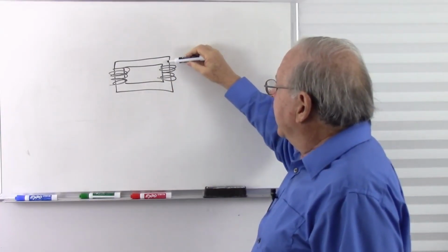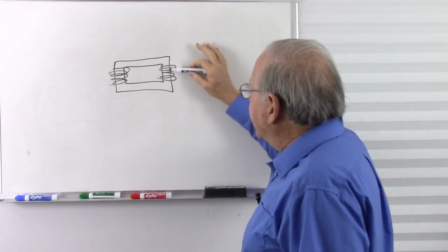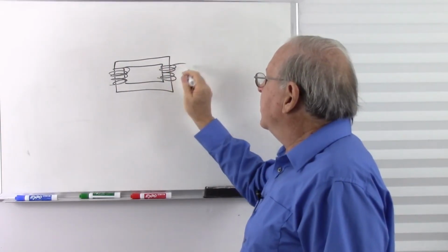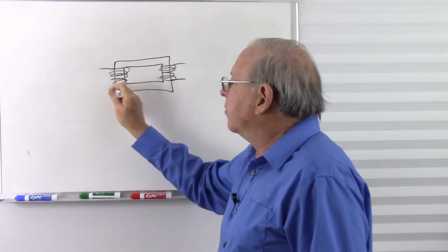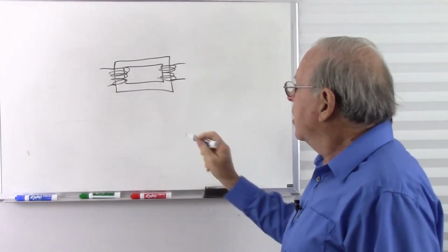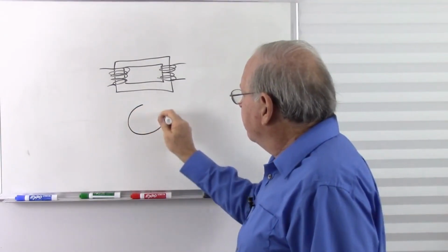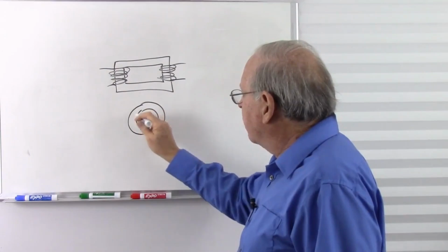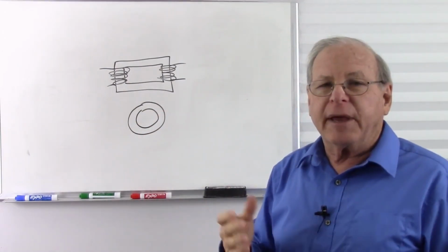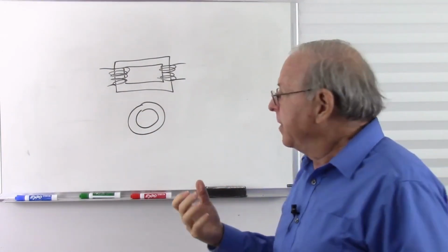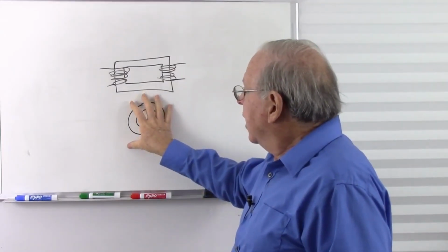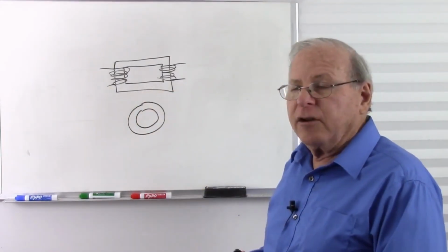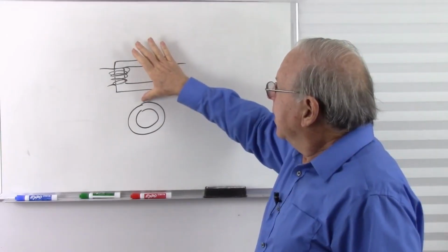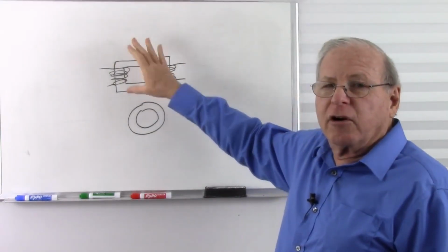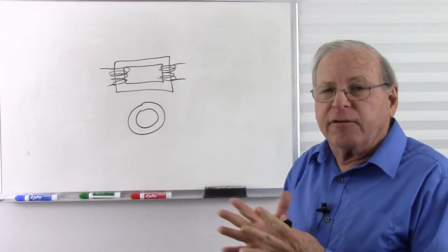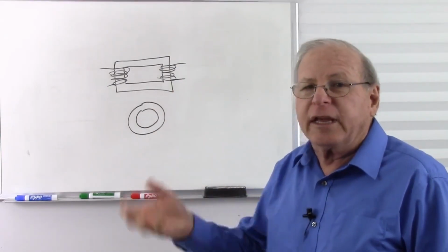The laminated iron will conduct the magnetic field across, but we have the coils further apart from each other, so we don't have as much capacitance. Another popular way of making isolation transformers is with a ferrite toroid. Ferrite is a material made of powdered iron and clay, and it has good electromagnetic properties for making transformers. The laminated steel plates here are coated in lacquer so that they're insulated from each other, so we don't get currents flowing inside the core.